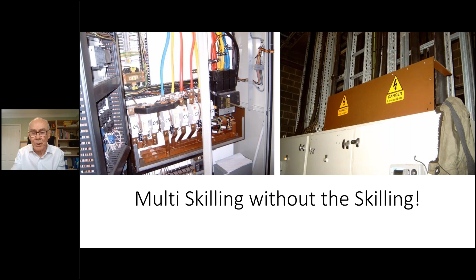This is coming to the end of those slides, but here's one where I got called out one Saturday. Two guys ended up hospitalised after initiating an arc flash in a panel that was still live. They had a Saturday morning job to clean this panel, and instead of isolating it upstream, they relied on local isolation. The panel isolator, as you can see if I circle it, had the actuator bar and shrouding missing — there's a common thread here, isn't there? The workers thought the outgoing retrofitted switch on the right-hand side of the panel was the main isolator, which it wasn't.